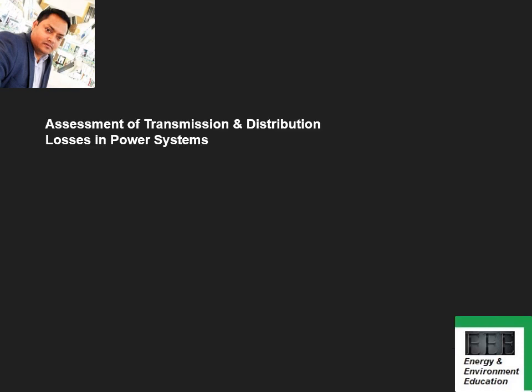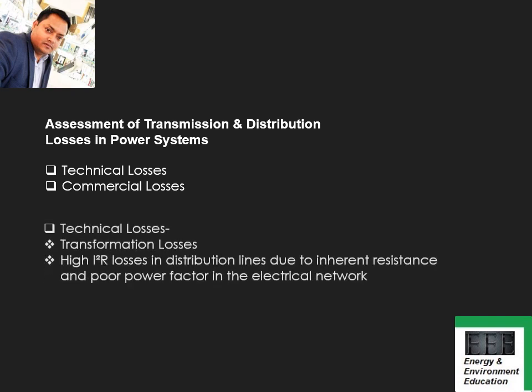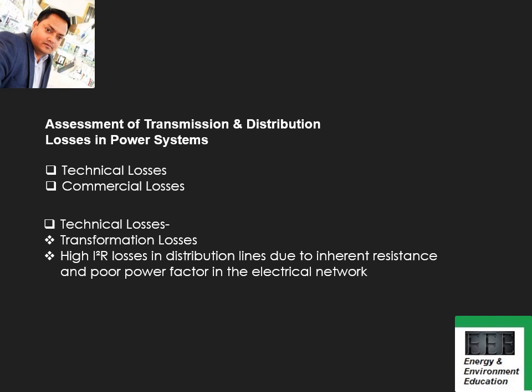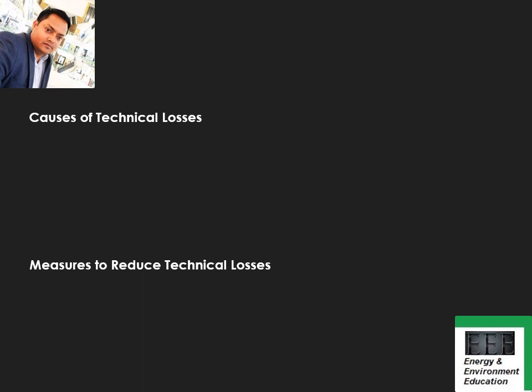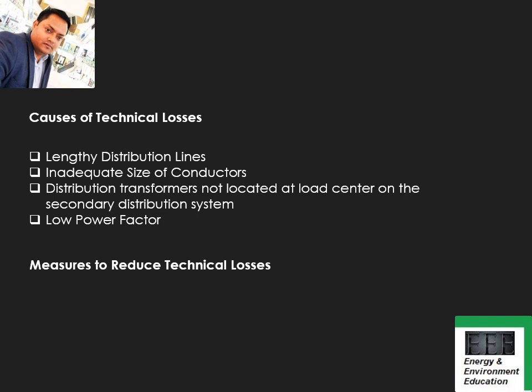As far as transmission losses in the power system are concerned, there are two types: technical losses and commercial losses. Technical losses include transformation losses and I²R losses. There are four causes of technical losses: first, lengthy distribution lines; second, inadequate size of conductor; third, distribution transformers not located at the load center on the secondary distribution system; and fourth, low power factor. You may be asked short questions or to explain briefly the different causes of technical losses.